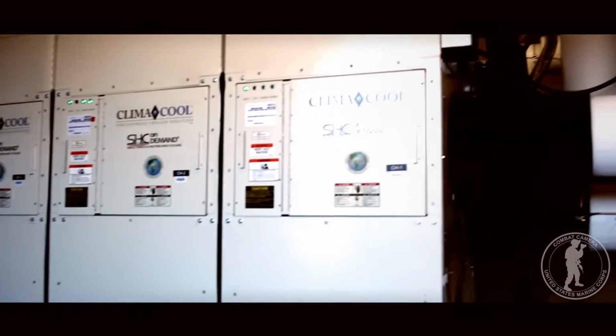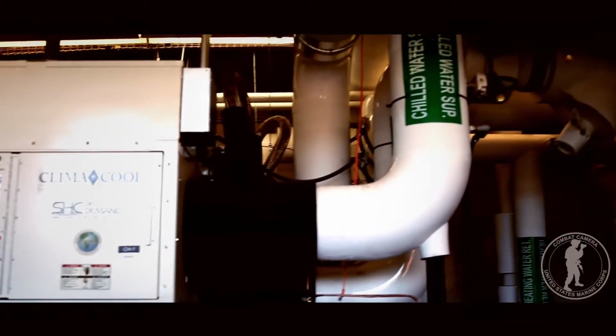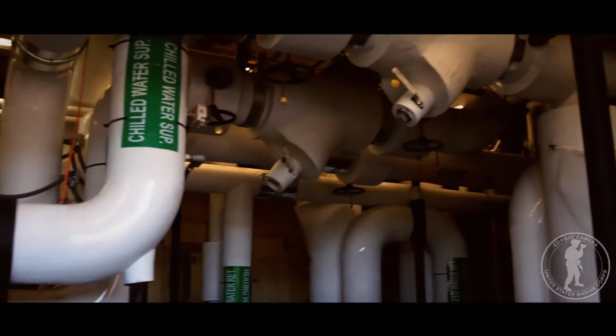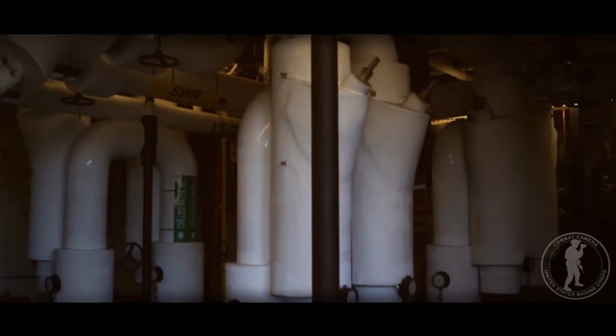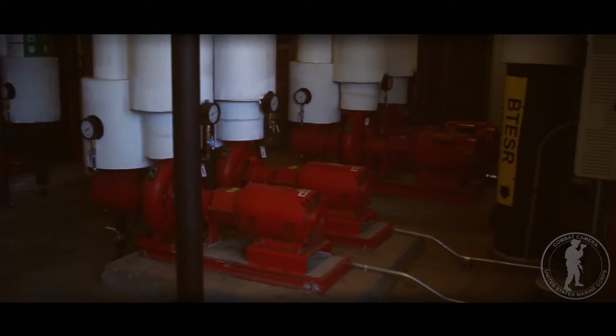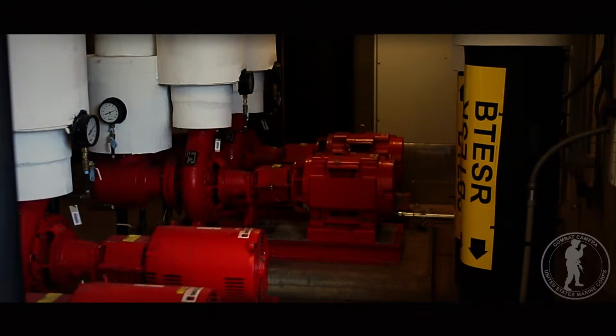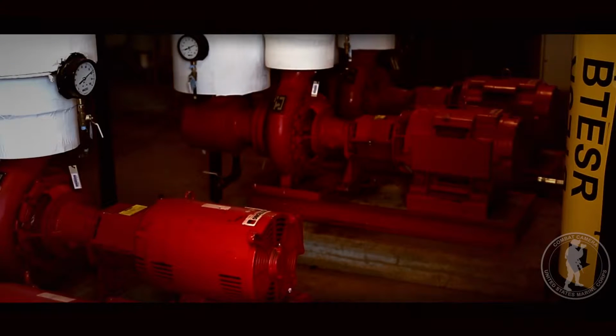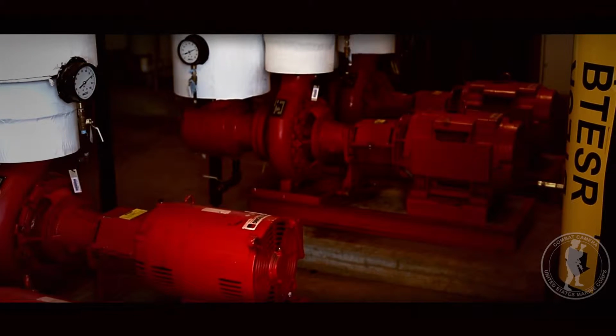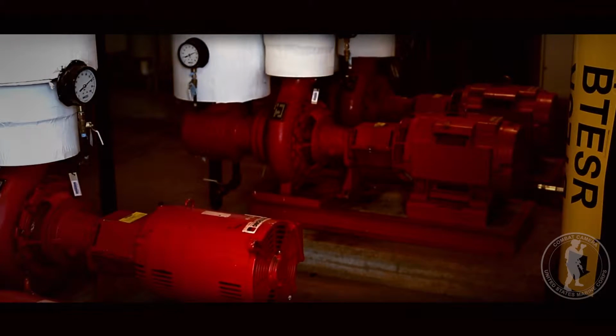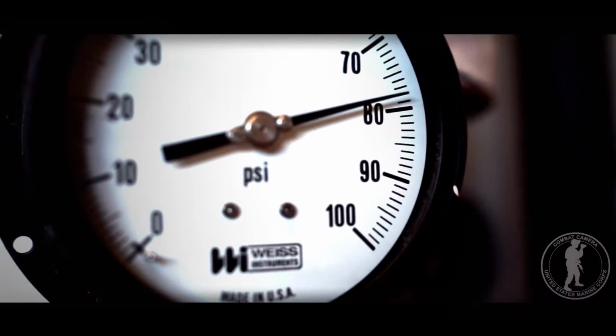Building 3700's mechanical room contains state-of-the-art heating, ventilation, and air conditioning equipment, which consists of 5 dual water-cooled heat pumps for a total capacity of 425 tons, and 2 chill water supply and return pumps for maintenance redundancy. Heating is provided by a 4-row distributed variable air volume system using water at 105 degrees Fahrenheit.